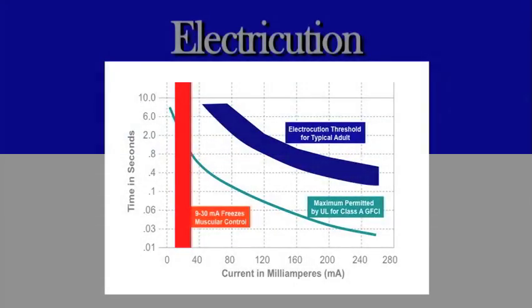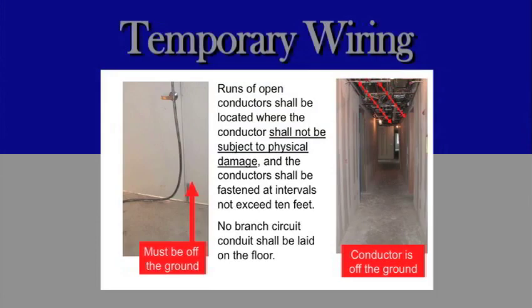Electrocution. Time until fibrillation can start. Temporary wiring. Runs of open conductors shall be located where the conductors shall not be subject to physical damage, and the conductors shall be fastened at intervals not to exceed 10 feet. No branch circuit conduit shall be laid on the floor. Must be off the ground. Conductor is off the ground.